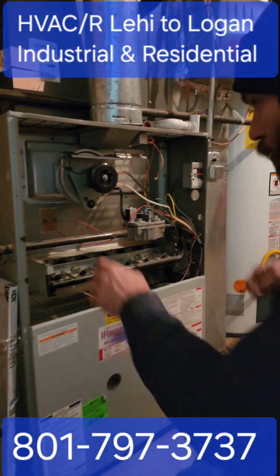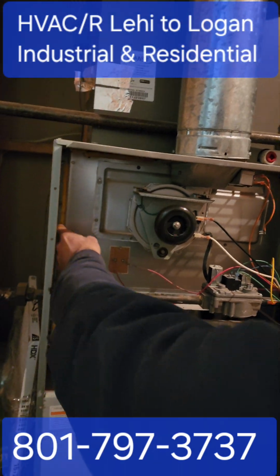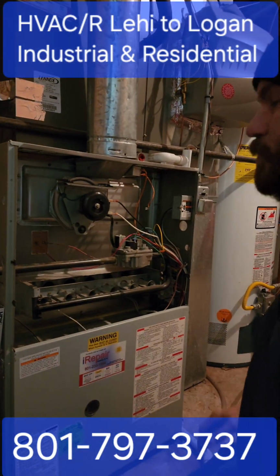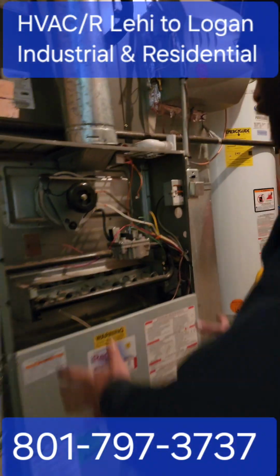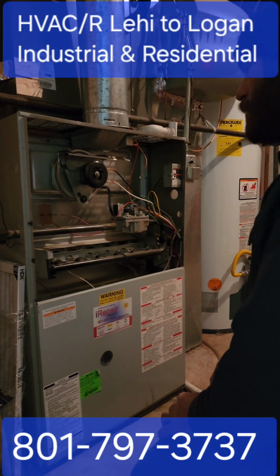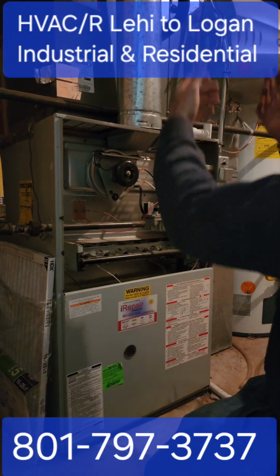But if you look, you can see screws here all the way around the edge. Yeah. And this fiberglass poking through. Yeah. That whole thing comes out. And that's how you change the heat exchanger? But you have to completely disassemble the whole furnace to get that out. Because the fan's down below, it blows air up across it. And the heat exchanger's hot, so that's how that works.